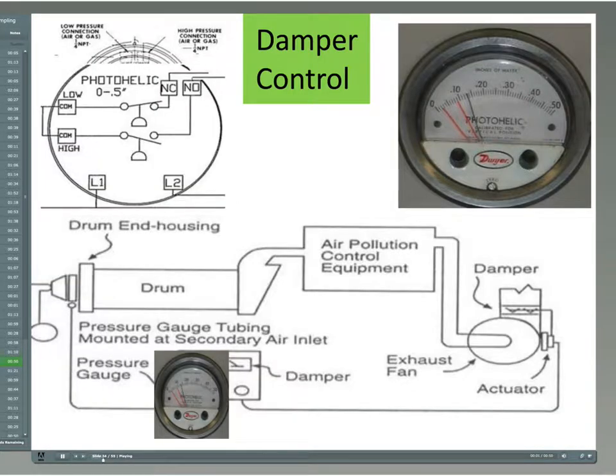This is a closed-loop control. This controller is placed in a damper control application. The controller, the Photohelic, is more than a pressure gauge. It has 2 red needle set point switches that actuate when the black needle passes over the red needles as the black needle fluctuates with the changing pressure. When the low set point is wired to energize the actuator open windings, and the high set point is wired to energize the actuator closed windings, the flow of exhaust gases through the drum can be controlled.